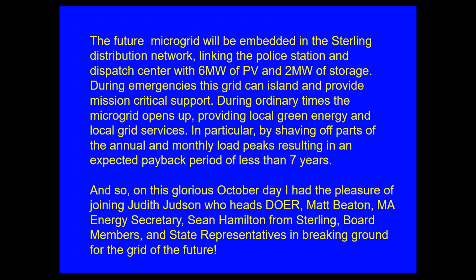Next slide please. The Future Microgrid will be embedded in the Sterling distribution network, linking the police station and dispatch center with 6 megawatts of PV and 2 megawatts of storage. During emergencies, this grid can island and provide mission-critical support. During ordinary times, the microgrid opens up, providing local green energy and local grid services, in particular by shaving off parts of the annual and monthly load peaks, resulting in an expected payback period of less than 7 years.